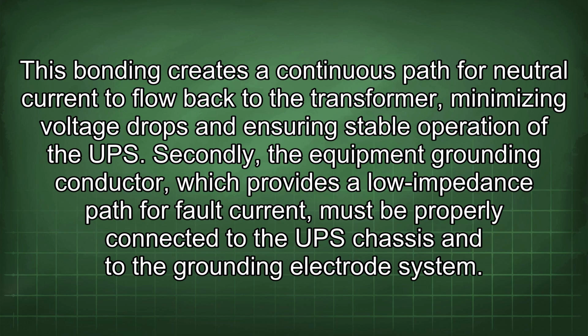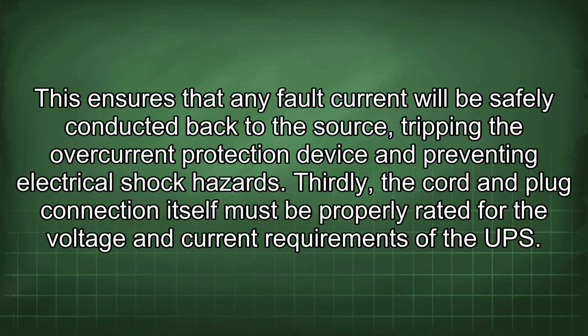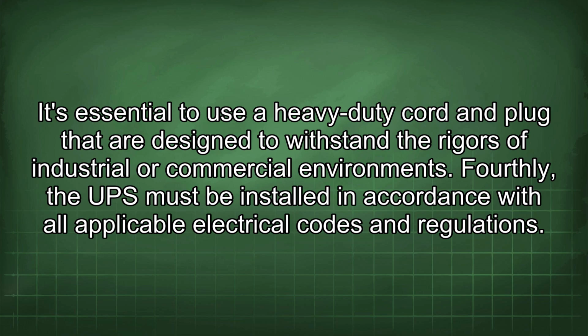Secondly, the equipment grounding conductor, which provides a low impedance path for fault current, must be properly connected to the UPS chassis and to the grounding electrode system. This ensures that any fault current will be safely conducted back to the source, tripping the overcurrent protection device and preventing electrical shock hazards. Thirdly, the cord and plug connection itself must be properly rated for the voltage and current requirements of the UPS. It's essential to use a heavy-duty cord and plug that are designed to withstand the rigors of industrial or commercial environments.